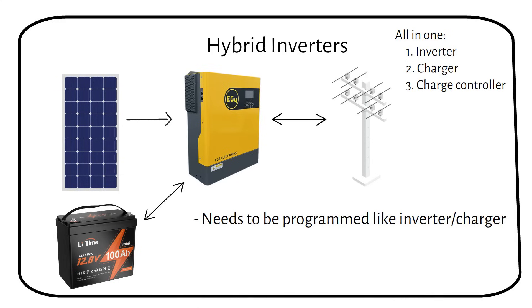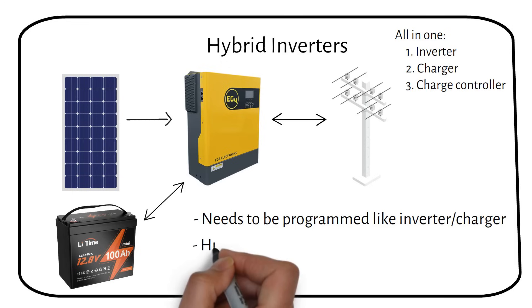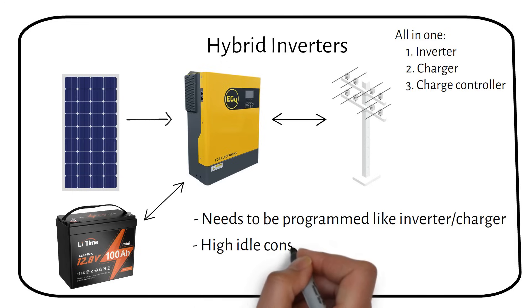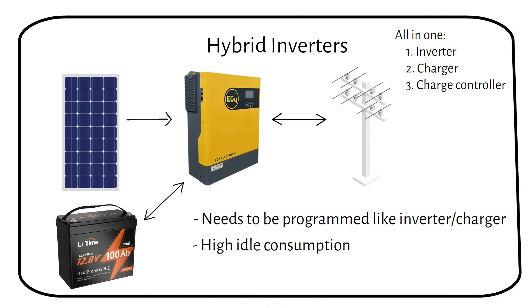Setting up a hybrid inverter involves more complexity than an off-grid inverter, particularly because it must be programmed to comply with specific grid codes. One consideration when opting for a hybrid inverter is its idle power consumption, which tends to be higher than that of more basic inverters. For instance, a 2 kilowatt unit might consume around 30 watts when idle, while an 8 kilowatt unit could use up to 120 watts. This increased energy use should be taken into account when sizing your solar system.